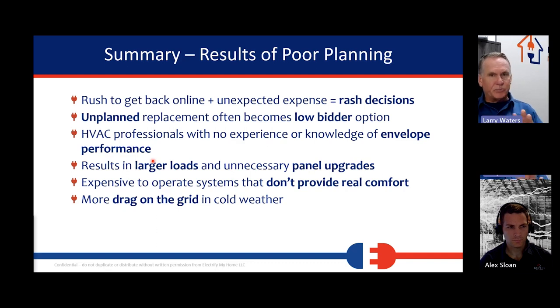But they put all this in, 6 breaker spaces used for this system that was horrendously oversized, and they had to get a new panel upgrade to get the system installed because it was going to take 6 breaker spaces. Well, when we got out there, the panel wasn't going to be the right capacity because they didn't up the capacity of the panel. Now the guy wants a stove, a dryer, a heat pump water heater, and solar and batteries. He had to replace that panel and upgrade it to 200 amps. So the guy bought 2 new electrical panels in 2 years because he was steered the wrong way. So be careful about this. Knowledge is power. Okay.